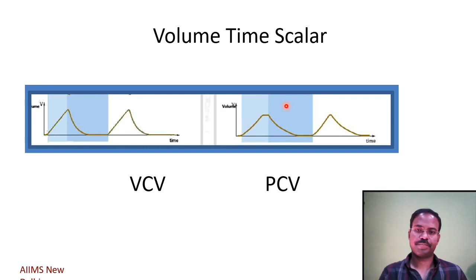And sometimes in the pressure control mode, you can notice a small plateau at the top of the volume time scalar. This is because the flow might have reached the baseline, but the inspiratory time is still continuing. So the tidal volume has already been delivered when the flow reached the baseline, but a small plateau occurs because the cycling has not yet occurred. However, if you have applied an inspiratory hold at the end of inspiration in the VCV mode, then you can also see this kind of pattern in VCV mode.